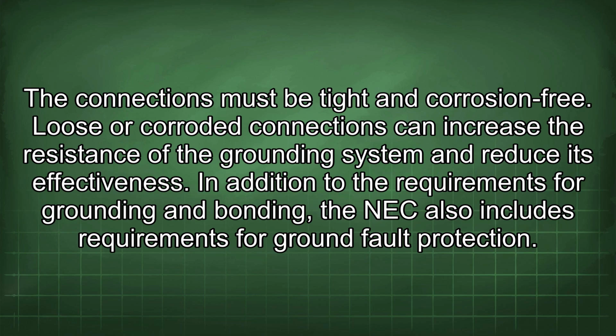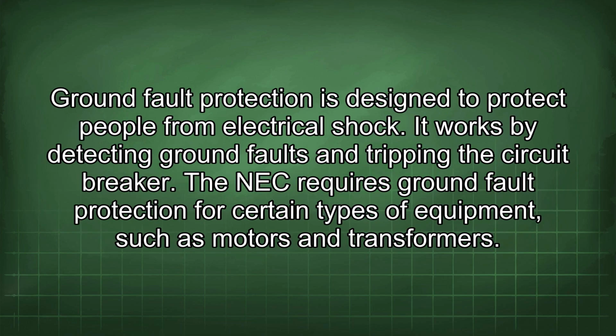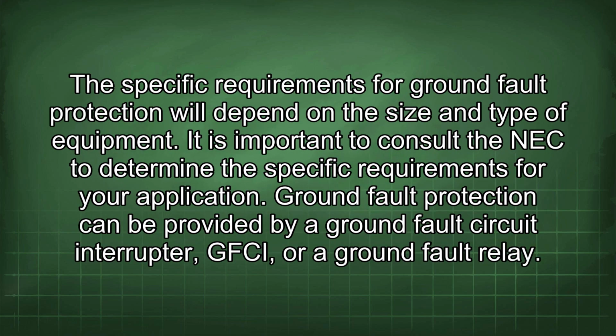In addition to the requirements for grounding and bonding, the NEC also includes requirements for ground fault protection. Ground fault protection is designed to protect people from electrical shock. It works by detecting ground faults and tripping the circuit breaker. The NEC requires ground fault protection for certain types of equipment, such as motors and transformers. The specific requirements for ground fault protection will depend on the size and type of equipment. It is important to consult the NEC to determine the specific requirements for your application.